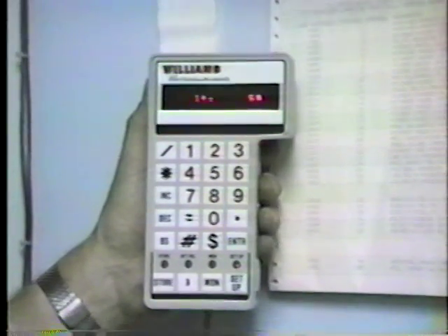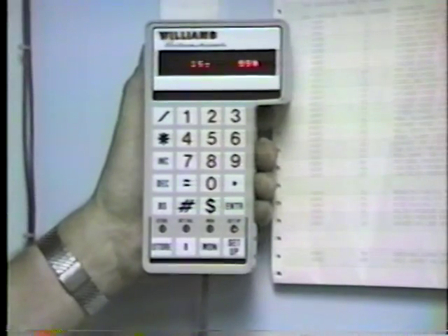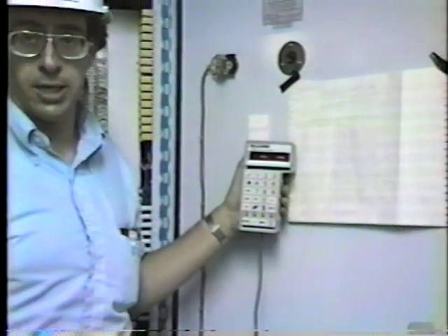14 is the spinner speed maximum increase. Up above on number 6, we had the spinner speed maximum decrease. We now have the maximum increase. This is how much we allow the spinner to speed up per second. Okay, that should not be changed, 5%. Number 15 is the spinner speed maximum command, and we've allowed for the full range of spinner up to 99%. All right.